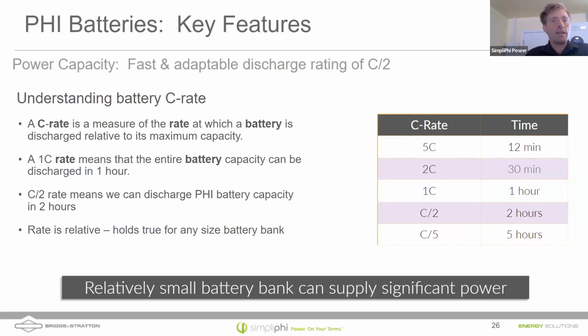So keep in mind, we talked about this briefly at the beginning, but the C rate on that PHI battery is still C/2. So it's a C/2 rating, which means it can be charged up in 2 hours. But that depends on your charging equipment, right? If your charging equipment is only capable of supplying a lower current than the maximum rate the battery can accept, it'll take longer to charge the battery.